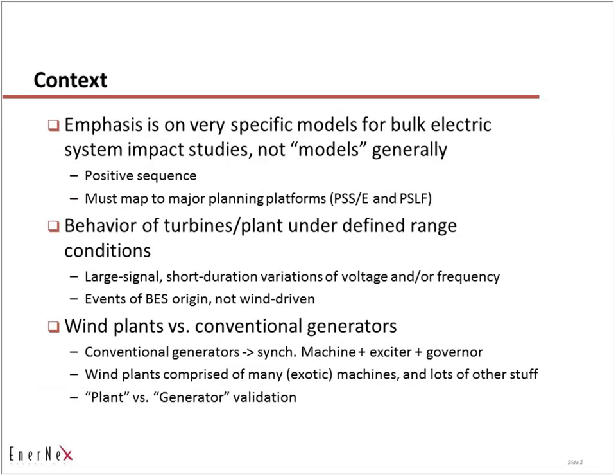When we look at VG plants relative to conventional generators, a couple of things pop out quickly. In conventional plants, we have one or maybe a few very large synchronous machines with well-characterized excitation systems and governors. With renewable plants, we have a very large number of relatively exotic machines, plus lots of other infrastructure to connect the individual sources of renewable generation to a delivery point to the grid.